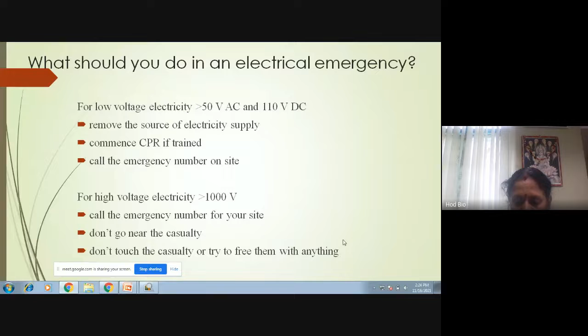For low voltage electricity, greater than 50 volts AC or 110 volts DC, just remove the electrical supply using the circuit breaker, then call the emergency number on site. Take these steps. If the voltage is very high, greater than 1000 volts, call the emergency number. Don't go near the casualty casually, and don't touch the casualty or try to free them with anything.